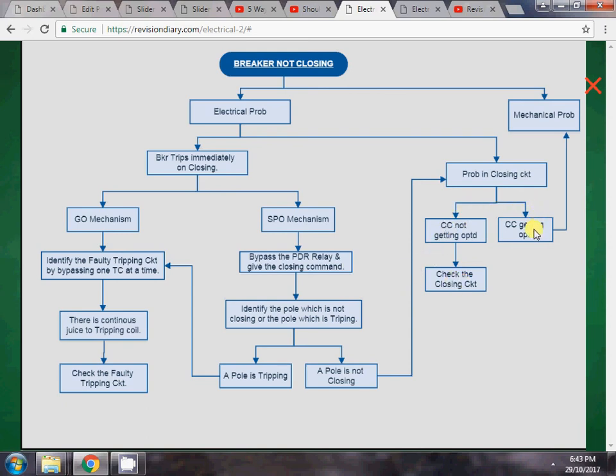If the closing circuit is getting operated and still the breaker is not closing, then there is definitely a mechanical problem. This is how we can troubleshoot the breaker not closing problem.